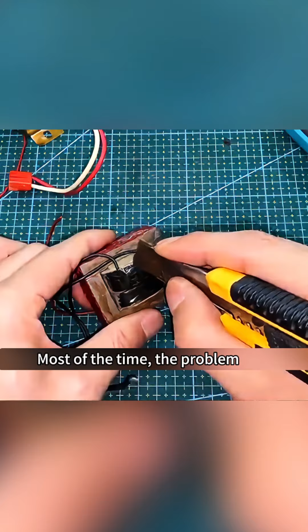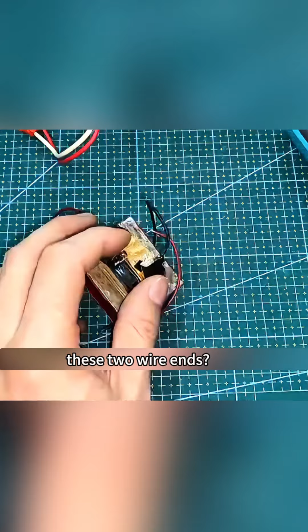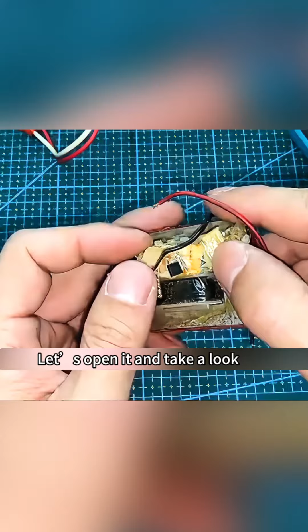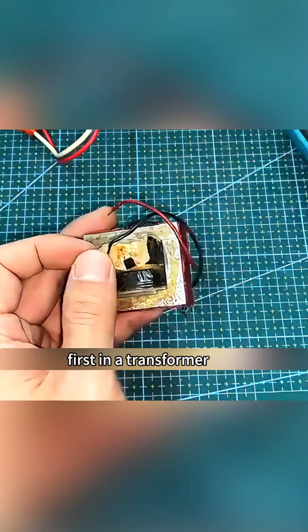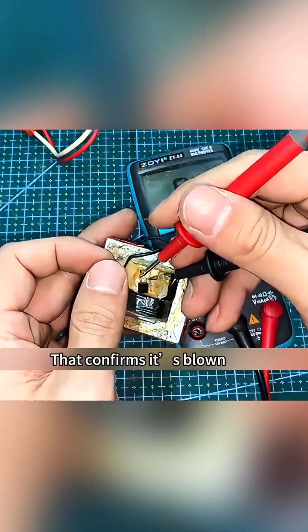Most of the time, the problem is the protection inside the coil. Look at this black part, see these two wire ends, it feels a bit swollen. Let's open it and take a look. Inside there's a thermal fuse. This is usually what breaks first in a transformer. Test it with a multimeter, you see nothing, that confirms it's blown.